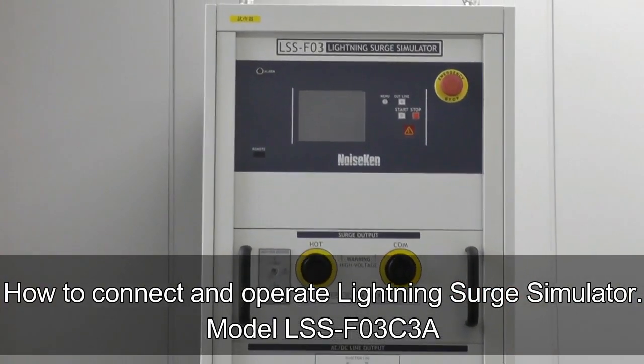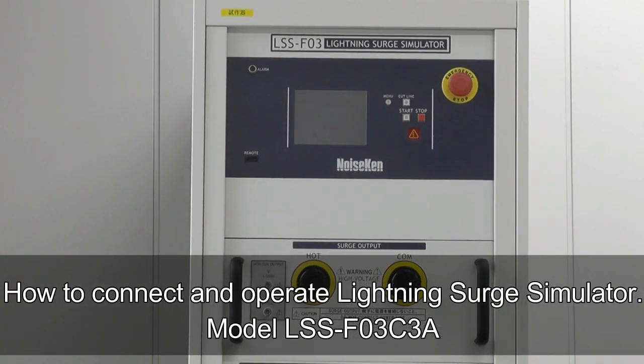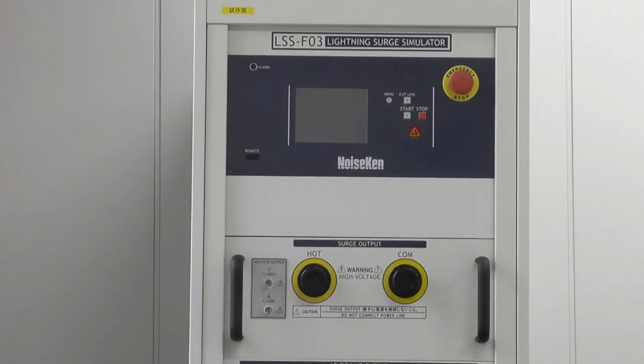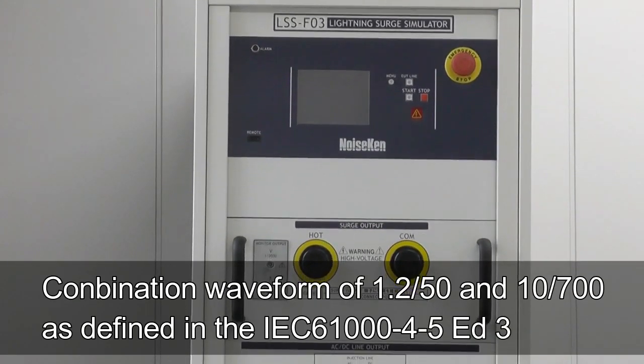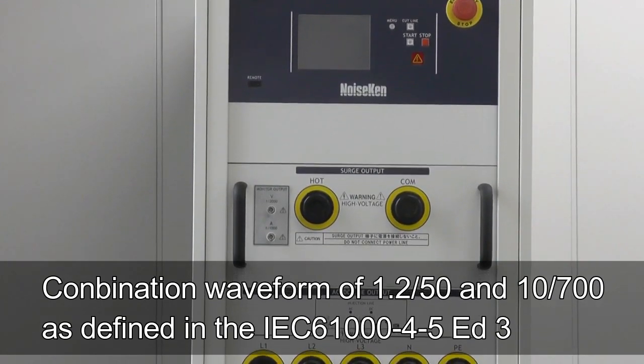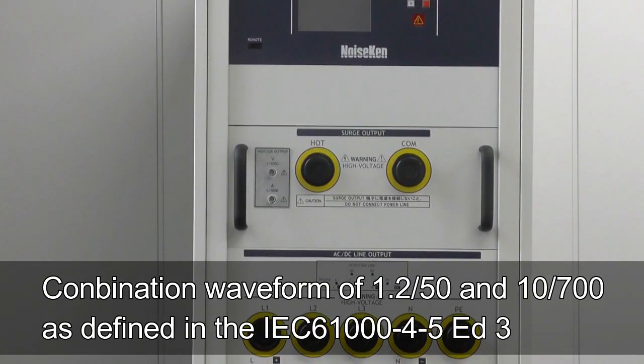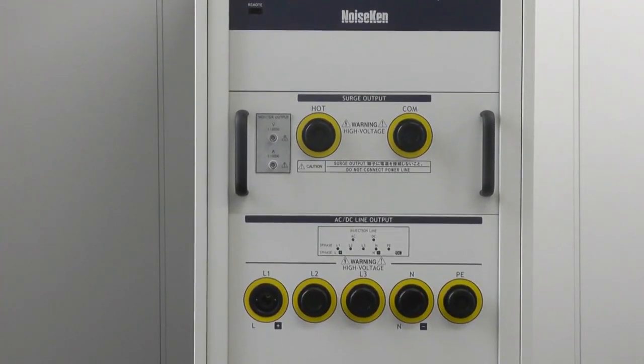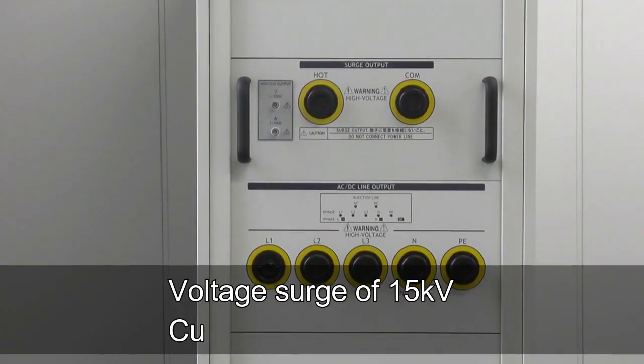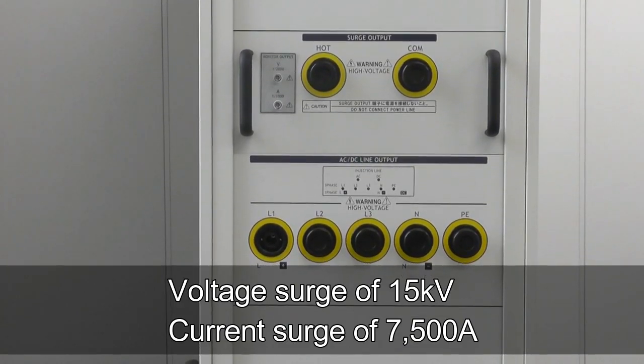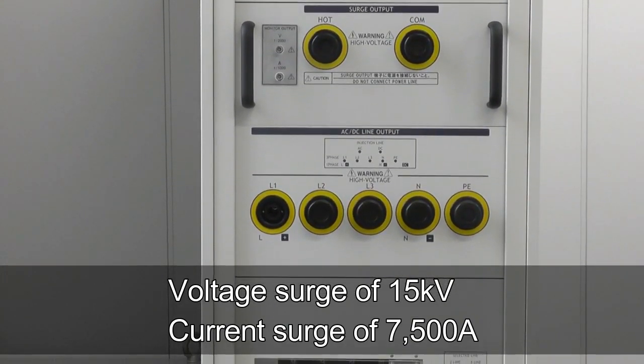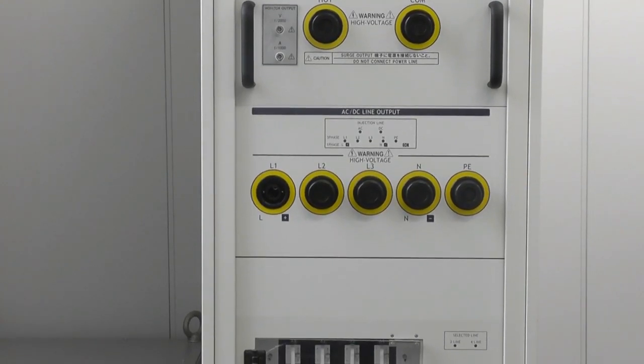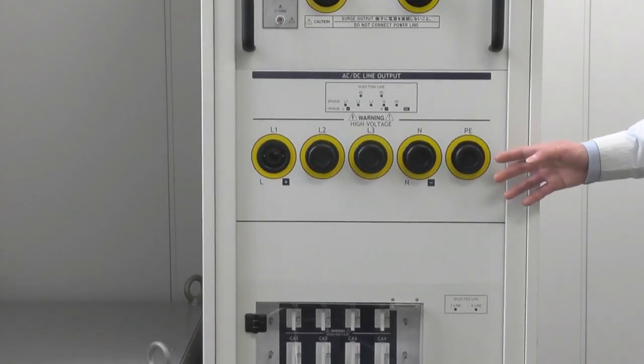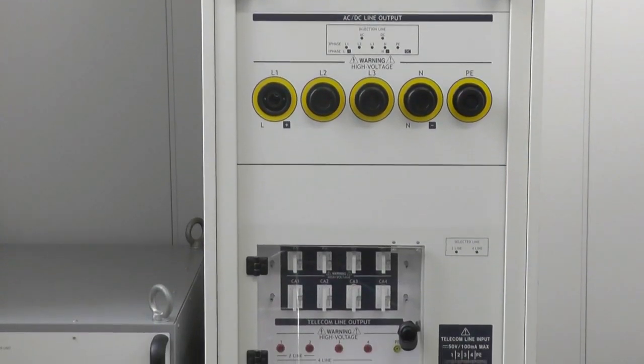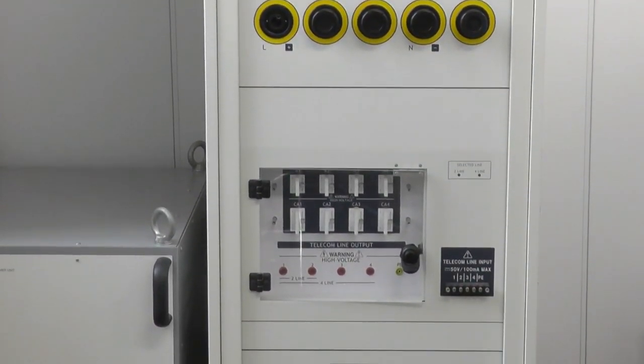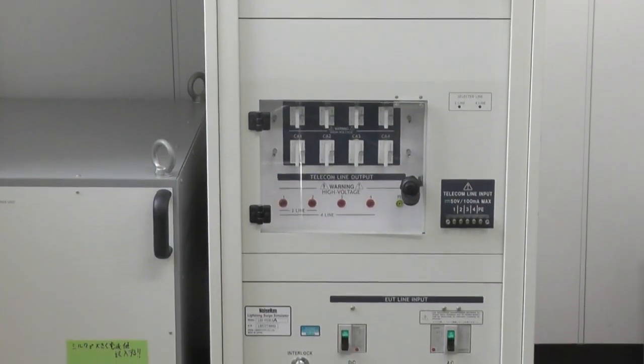This is the lightning surge simulator LSS-F03C3A, capable of generating the combination wave of 1.2/50 and 8/20 µs as defined in IEC 61000-4-5. It offers high voltage, high current tests with a voltage surge of 15 kV and a current surge of 7,500 amperes, with a built-in CDN for power line surge testing, as well as a built-in CDN for symmetrical interconnect lines, which allows for surge testing of the telecom lines.